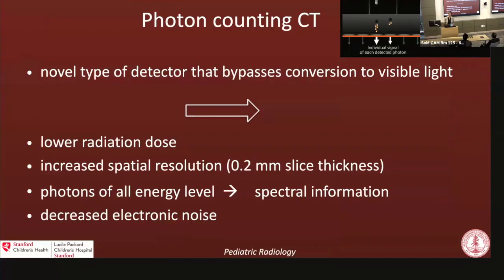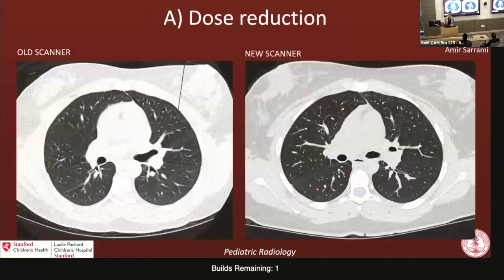in the human body. We can also detect photons of all energy levels, and we can tell what energy level we are seeing, and we can filter them, so then we can decrease the electronic noise. Because let's say if we have photons that are below 25 keV, we can say this is just noise, and please remove those from our pictures. So I will show you a couple of images to prove that it's not just words, but we have the proof. Here on the left is the non-contrast chest CT from the old scanner.